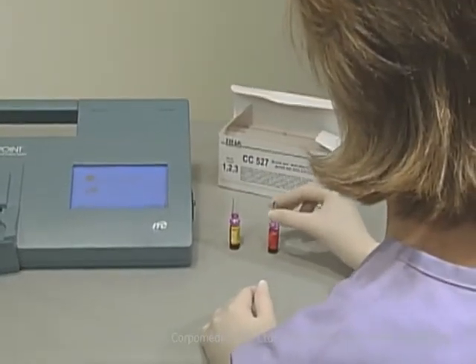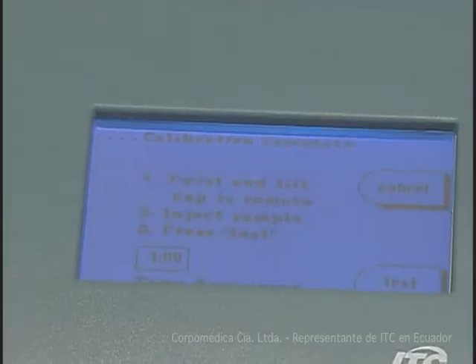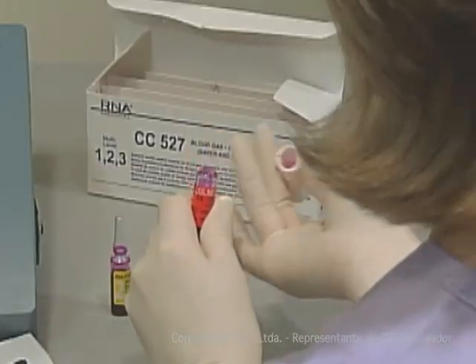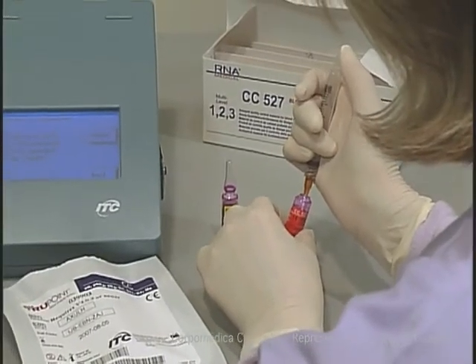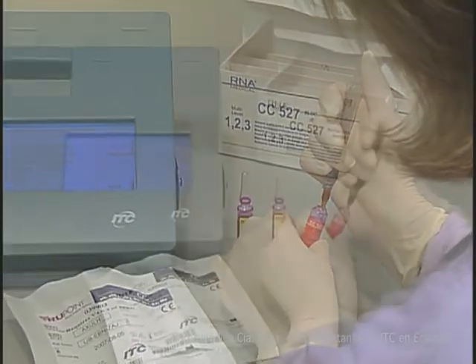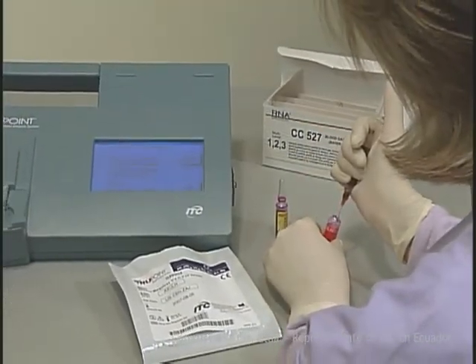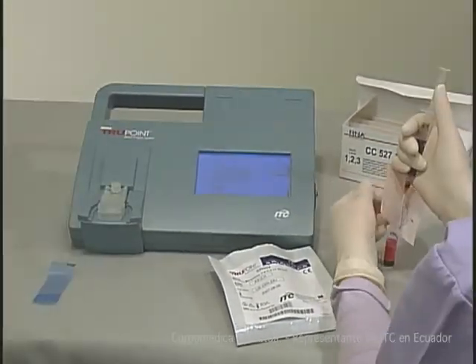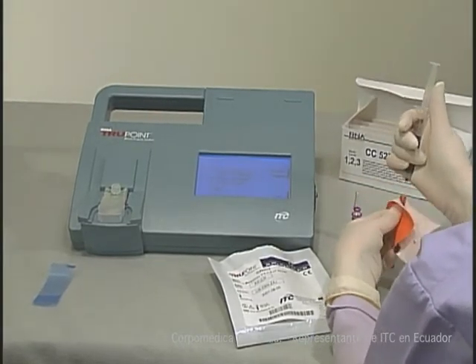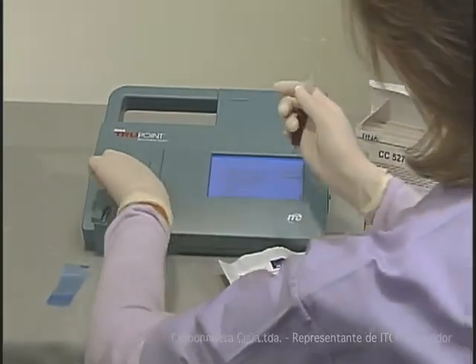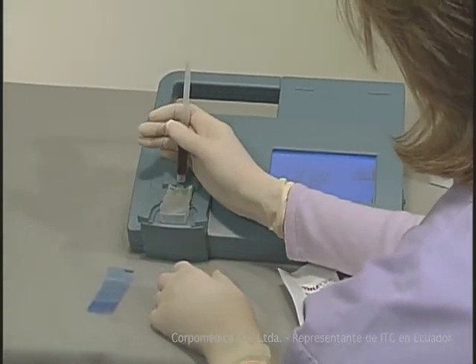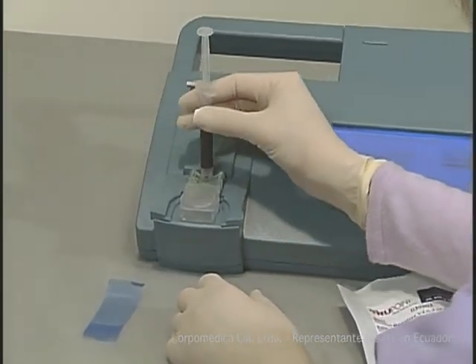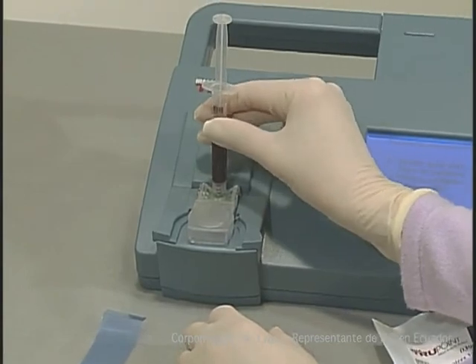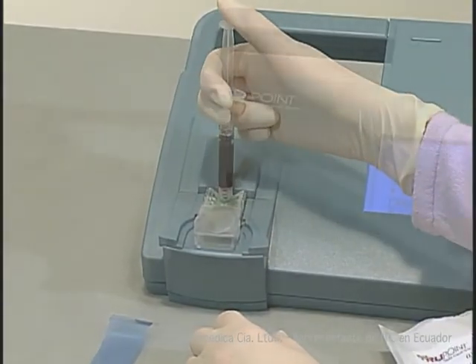After the cartridge calibration is completed, carefully snap open the control ampule. Draw the control sample into a non-heparinized syringe using an 18 to 20 gauge needle or plastic precision tip. Do not invert the syringe or attempt to remove any air bubbles. Remove the tip from the syringe and place the syringe in the cartridge luer port. Inject the sample and press Test. If the QC test is within limits, press Done. Document any results that are outside the QC limits.